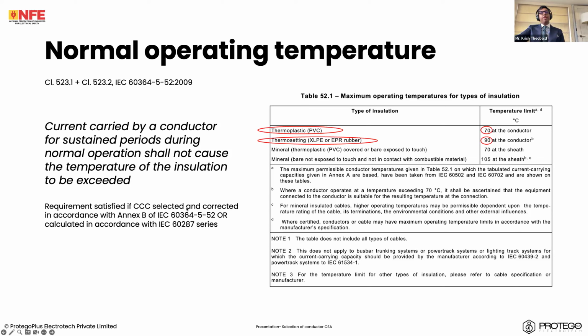This requirement is satisfied if the current carrying capacity is selected and corrected in accordance with Annex B of 60364-5-52, or of course calculated one of the other ways, the 60287 series. The important thing is that not only do they have to be selected, they have to be corrected as well. That is a very important part.